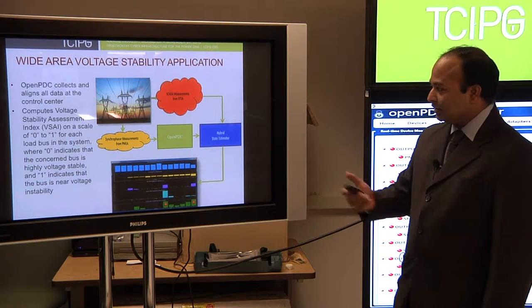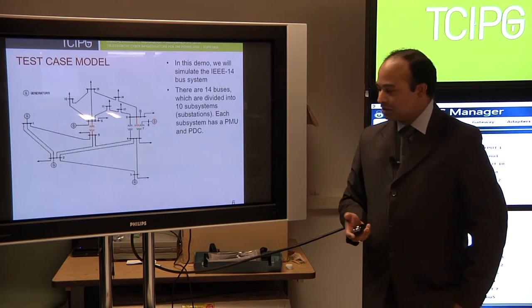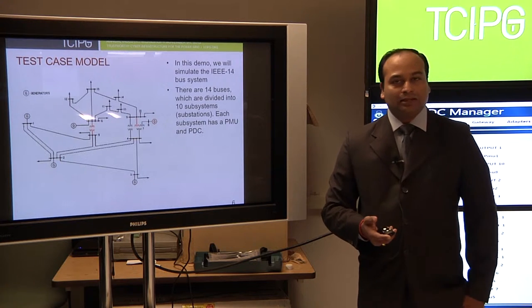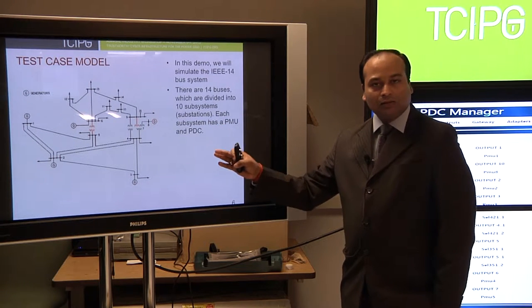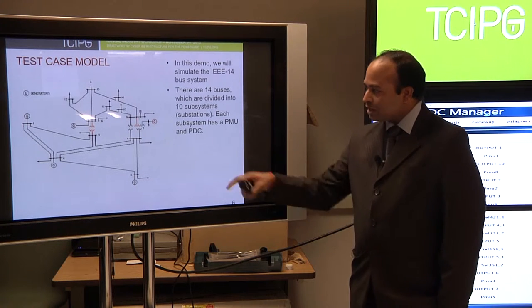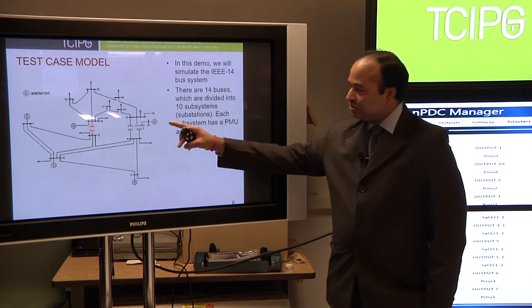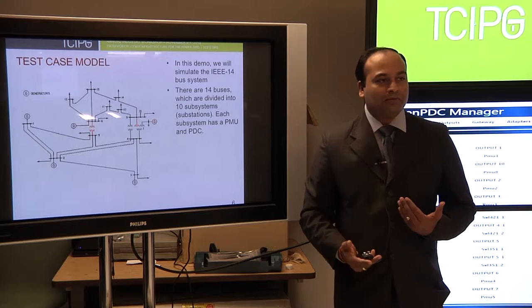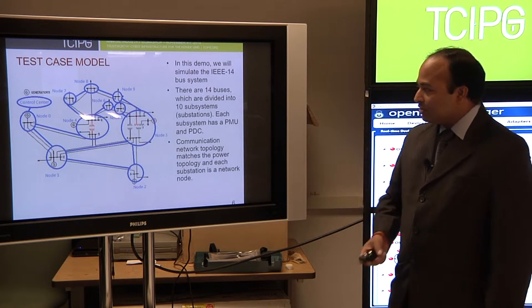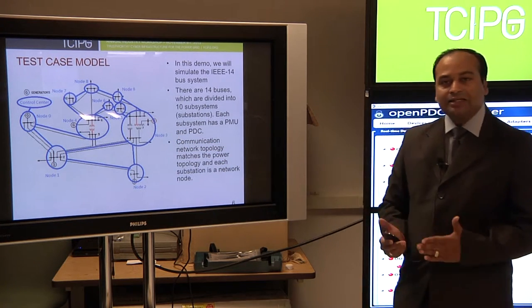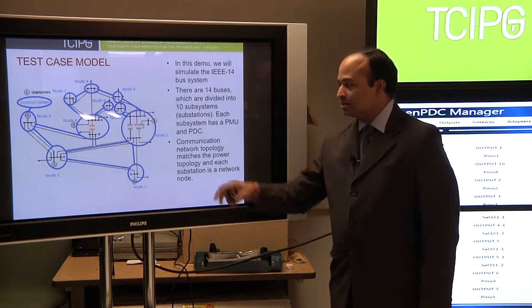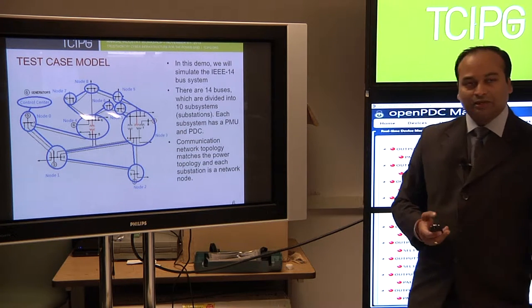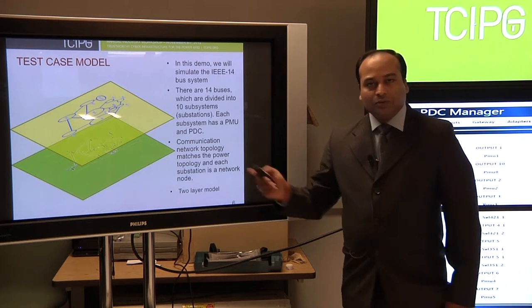Now the test case. We have IEEE 14 bus system, which is the standard IEEE system. We kept it small so that we can model the PMU at all the buses, either using hardware PMU or software PMU. You see 14 buses here, which we divide into 10 subsystems, which are basically substations. Each substation will have a PMU and PDC. On top of that, we put the communication layer. The communication network topology exactly matches with power system network, and then each substation is a network node in communication. So finally, what we have is a two layer model.